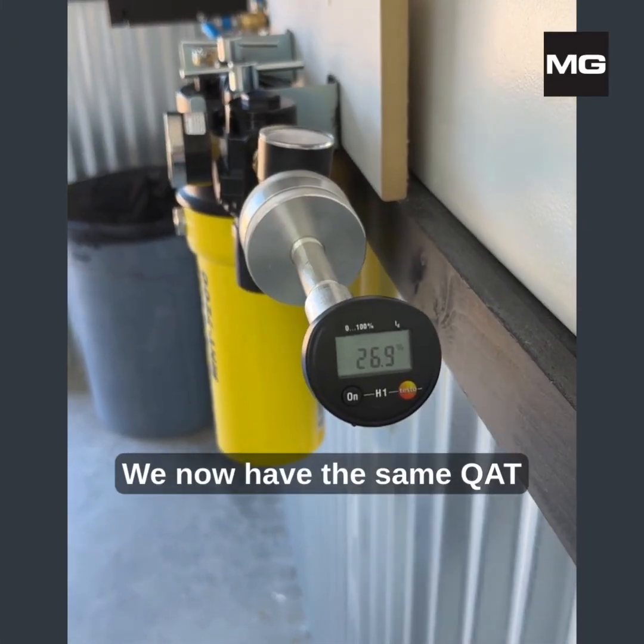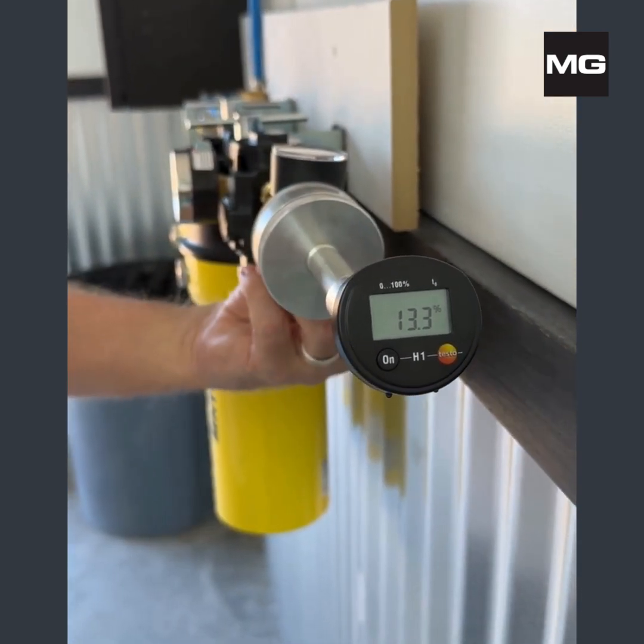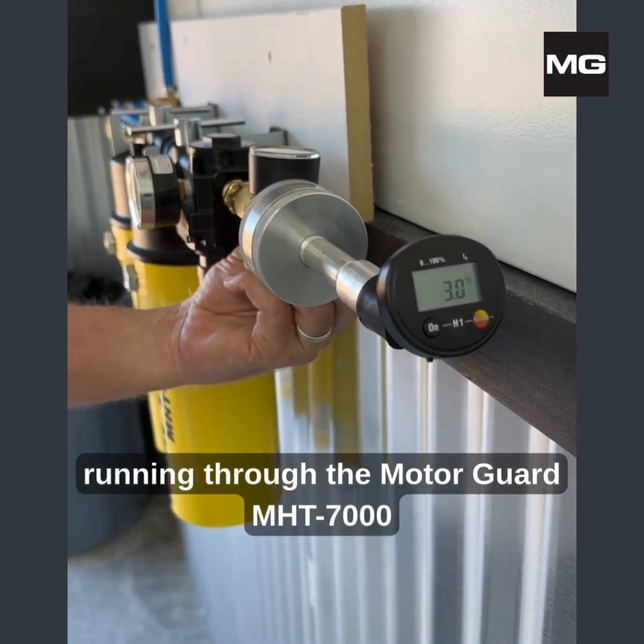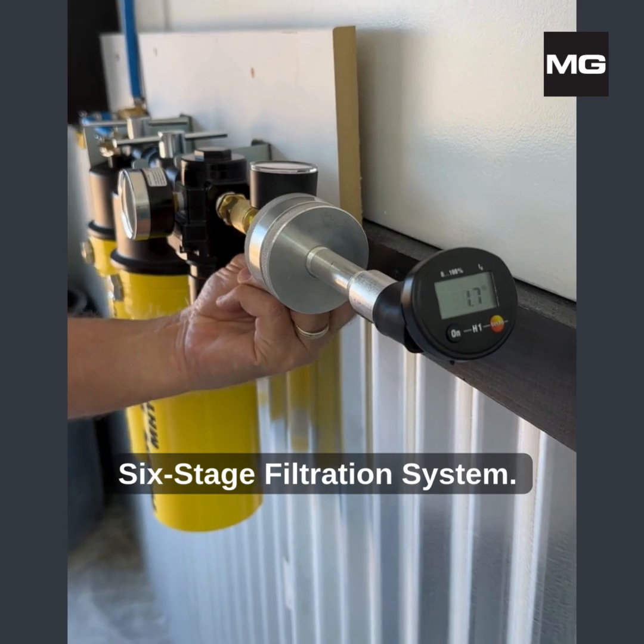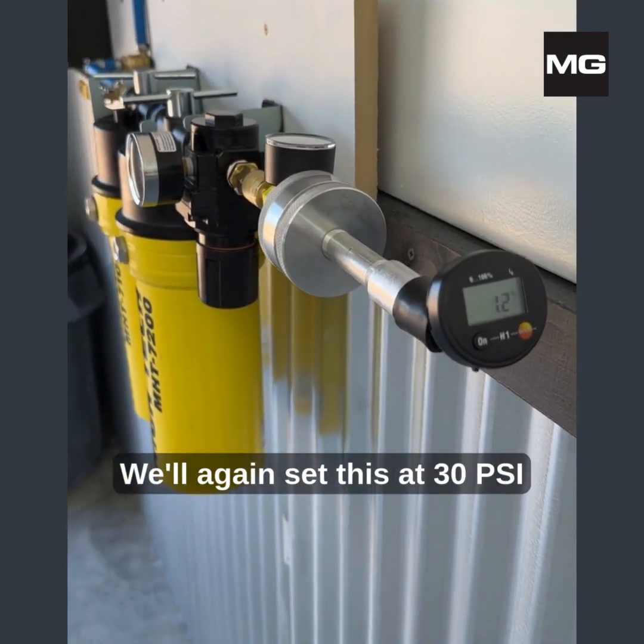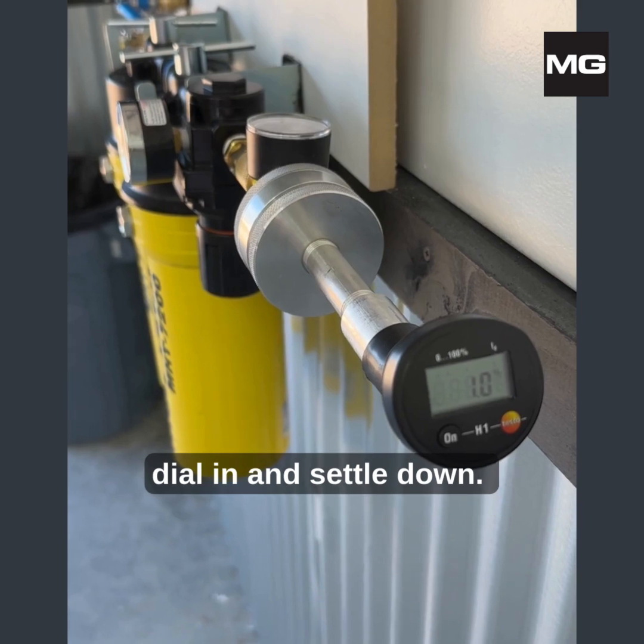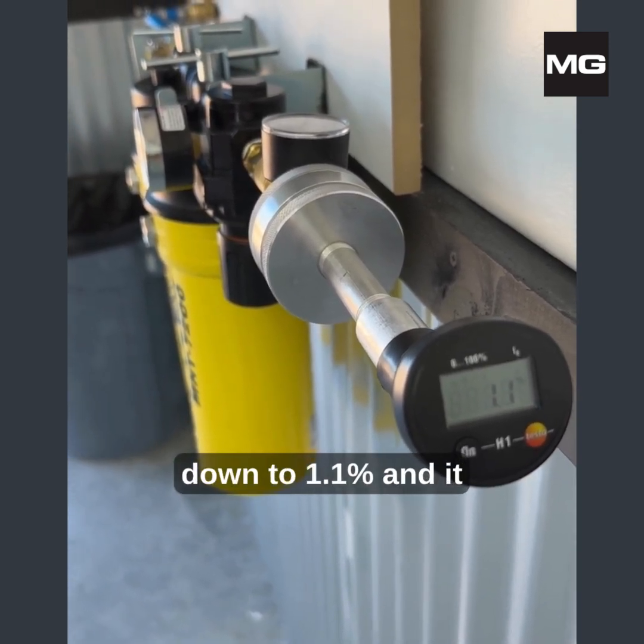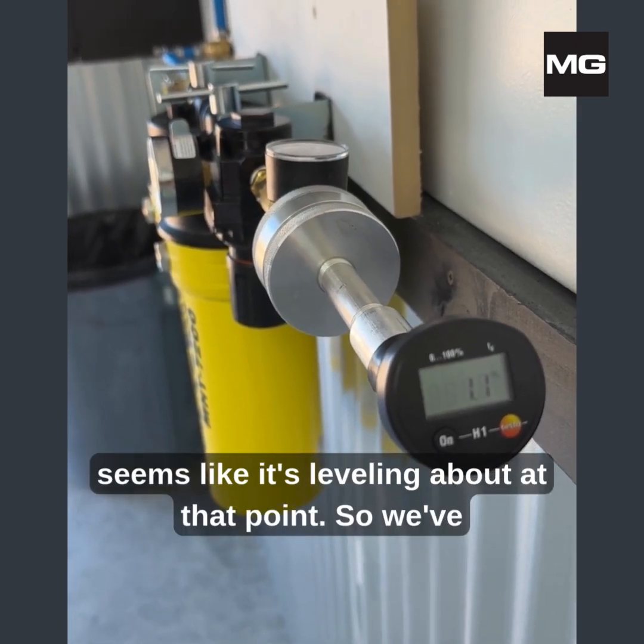We now have the same QAT test kit hooked up to the compressor, running through the MotorGuard MHT 7000 Six-Stage filtration system. We'll again set this at 30 psi and give it the same 15 to 30 seconds to dial in and settle down. As we can see, we're already down to 1.1%, and it seems like it's leveling off at that point.